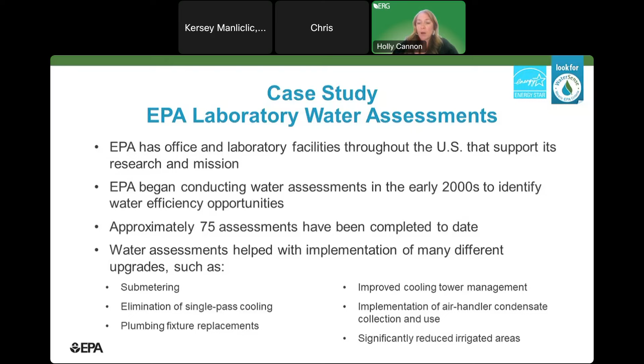Many facilities implemented an air handler condensate collection project, where they captured cool water from their air handler condensate and pumped it back to their cooling tower for makeup water. It's a really great matched end use. Air handler condensate is generated in the warmest months, and the cooling tower needs water in the warmest months, so it's a no-brainer if you can make that happen at your facility. We also helped them with a near elimination of irrigation water use.